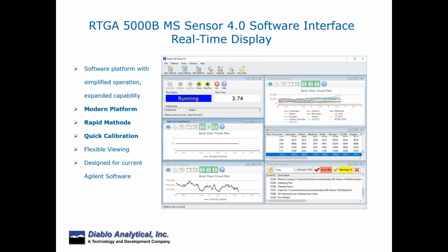This is what the screen looks like on the software. And so rather than having a gas chromatography type software, we have a process view in which the x-axis is now the time frame of your experiment. So we have different components you can see in the top right there. There's methane, nitrogen, oxygen, etc. And each of those represents that particular component that you're looking at, and it's based upon a particular mass to charge fragment that's from that component that's being looked at by the mass spec. This is a modern software platform, and it's very flexible and very easy to use.